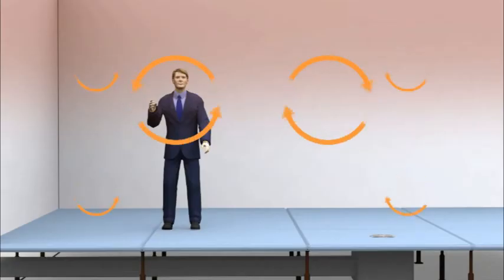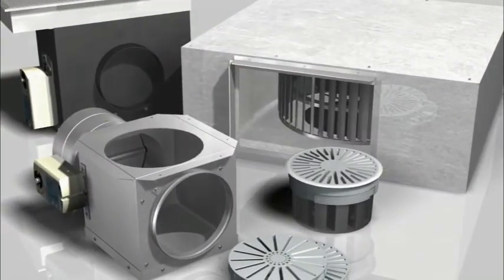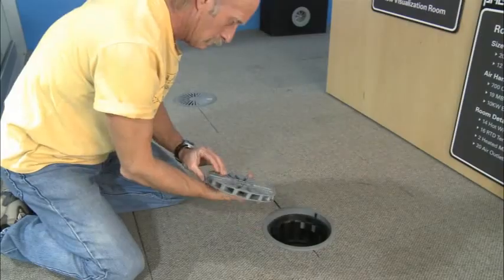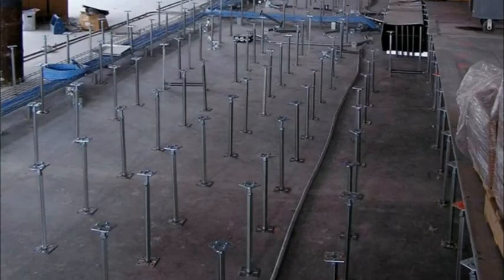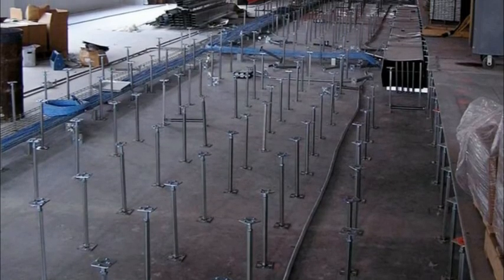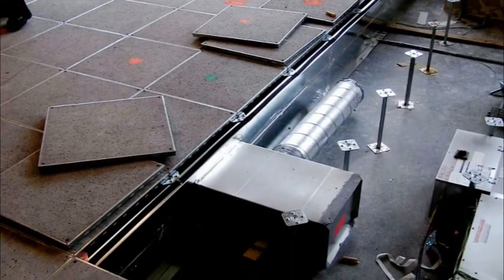Time modulation relies on the theory that perfect mixing is essential for effective underfloor air distribution — this is simply not true. ASHRAE recommends a maximum temperature difference from head to toe of an occupant of 5.4 degrees Fahrenheit or 3 degrees Celsius. As long as this condition is maintained, stratification is beneficial. Price offers the broadest product line in the UFAD market, including the only displacement flow underfloor diffusers, as well as unmatched applications support and on-site commissioning service to make your UFAD installation a success.